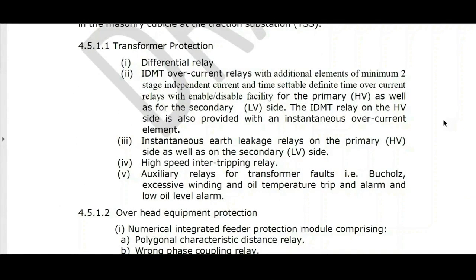When it is moving, in the path we keep one relay called the Buchholz relay. This relay will catch the bubble, identify what gas is inside, and issue a trip command. Depending on the contents of the gas, how much methane, how much ethane, how much nitrogen, how much oxygen, how much hydrogen, and depending on the analysis of this, we can also say what kind of fault has occurred inside the transformer. This is called oil diagnostics or transformer life management system.